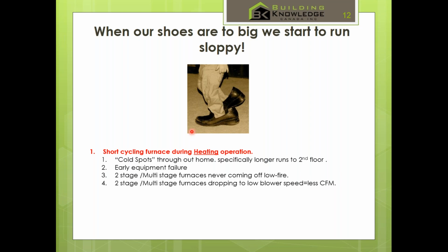So cold spots. The other thing too is we see multi-stage units never coming off low fire. And in these multi-stage units and even fully modulating units, we've seen short cycling, and these things actually never come off the lowest fire. And the problem with that is when your brand new furnace that costs you $5,000 more to purchase because it has full modulation comes on, the thermostat in the hallway tells it to keep shutting off after 5 minutes. It also goes to lowest fan speed, which means we're now running CFMs trying to move air through houses with only about 300 CFM of air with ductwork that's sized for 1,200.